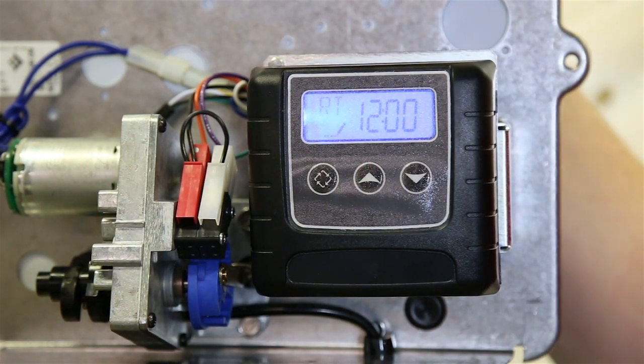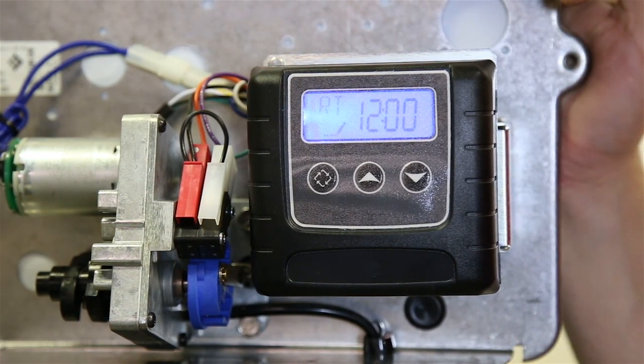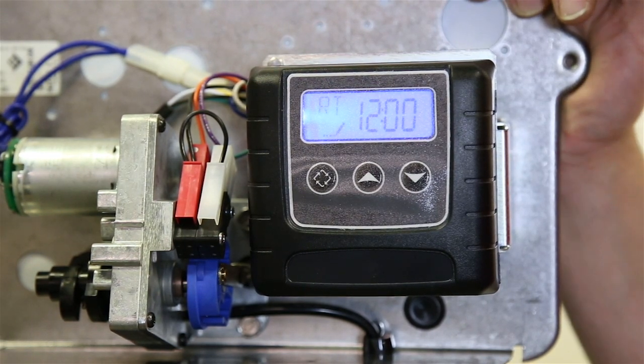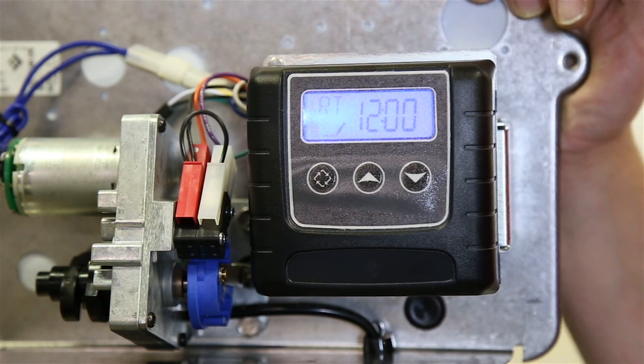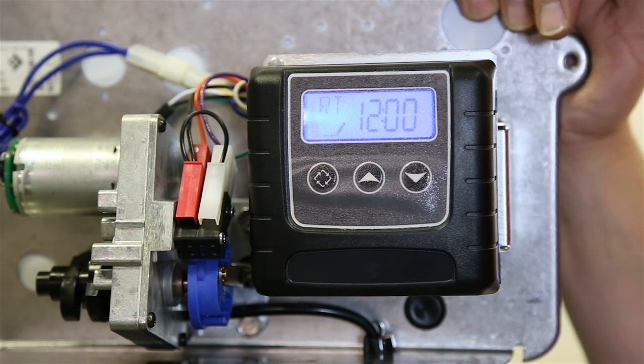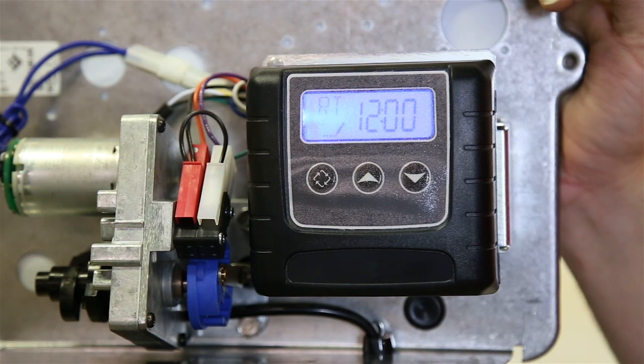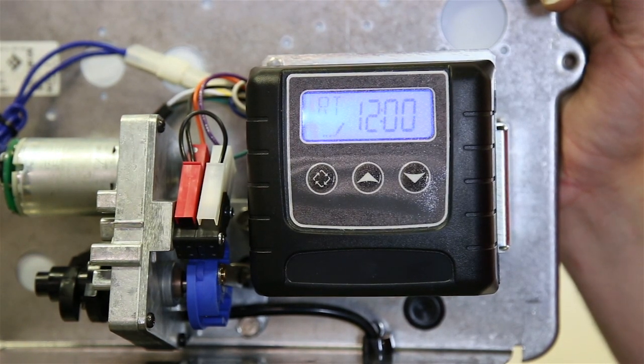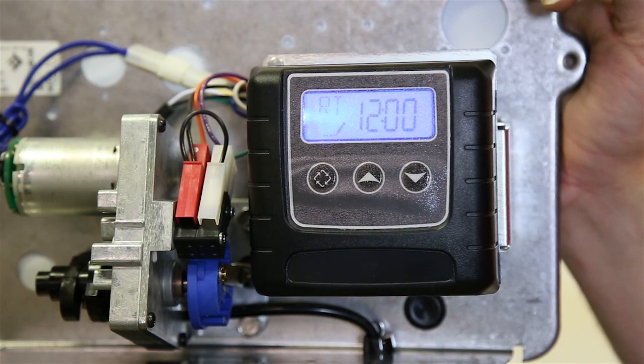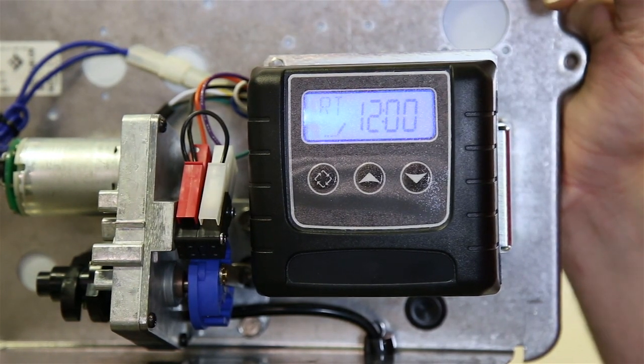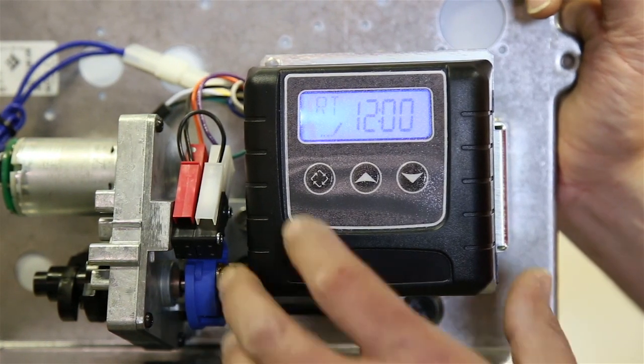Now this is the regeneration time. They're factory set up to regenerate at 12 AM. Typically water softeners are going to regenerate somewhere around 2 AM. This particular unit is going to take somewhere around an hour to regenerate. So you want to make sure it's done well before the softener regenerates. So I would say set this for at least an hour and a half before the softener regenerates to make sure that this is completely done if they both happen to regenerate on the same night.